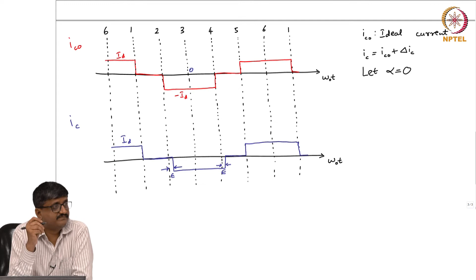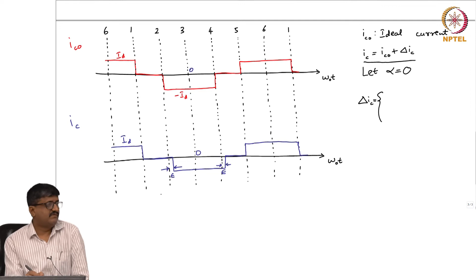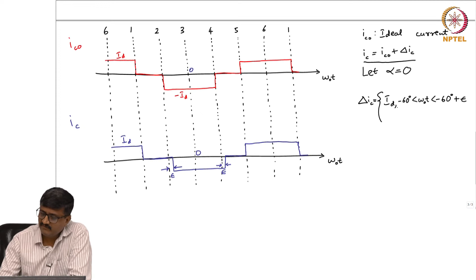Now, IC is given by the ideal ICO plus a deviation delta IC. Let us look at delta IC. If I want to know delta IC in one cycle, the deviation from the ideal case is only at two places, due to the firing angle error in valve 2 and in valve 4. Due to the firing angle error in valve 2, delta IC is non-zero and equal to ID for omega OT greater than minus 60 degrees (minus pi by 3) and less than minus 60 degrees plus epsilon. And there is one more error due to the firing angle delay in valve 4. That will result in delta IC equal to minus ID, from 60 degrees to 60 degrees plus epsilon.